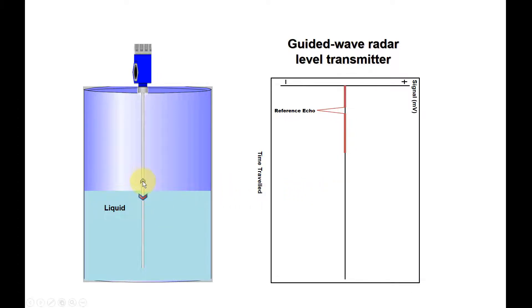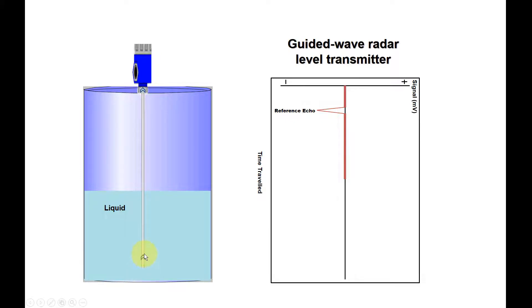Then you can see the signal bounce back and continue to move back to the level transmitter. This radar signal will continue to move down across the level probe. Meanwhile, we can see the waveform continue to move in such a way. Then it continues to move, and when it reaches the end of the level probe, it will travel back to the level transmitter. The liquid surface signal which was bounced back by the liquid surface will reach the level transmitter electronic board and be detected — hence you can see there's a liquid echo here, represented by the liquid surface.